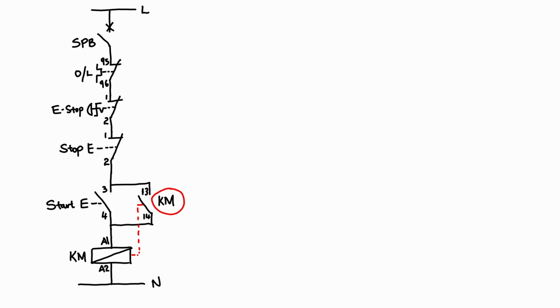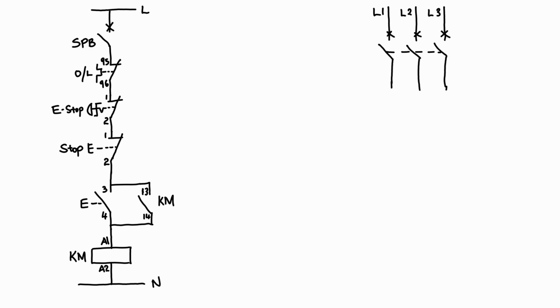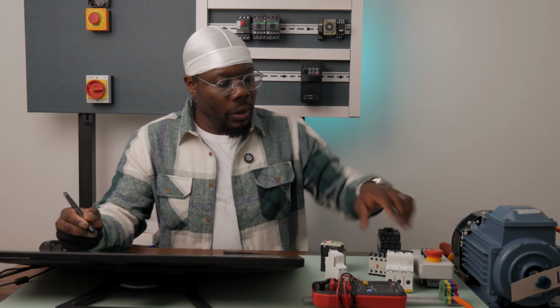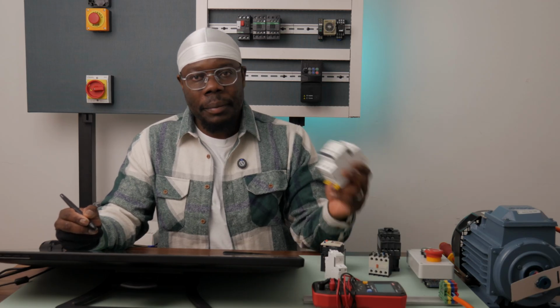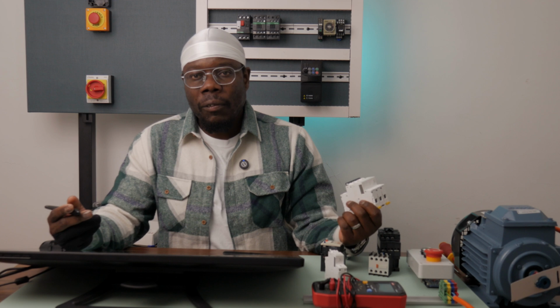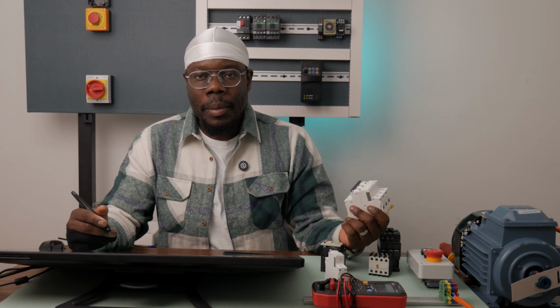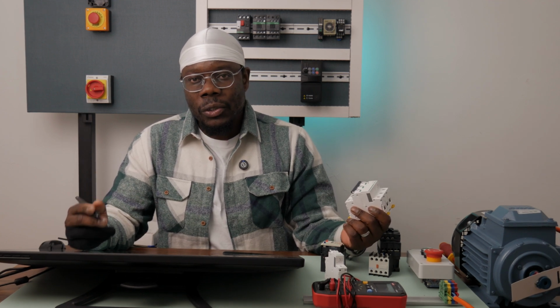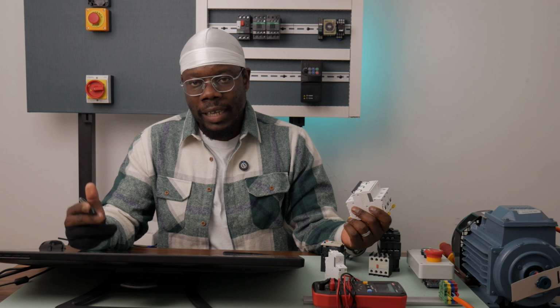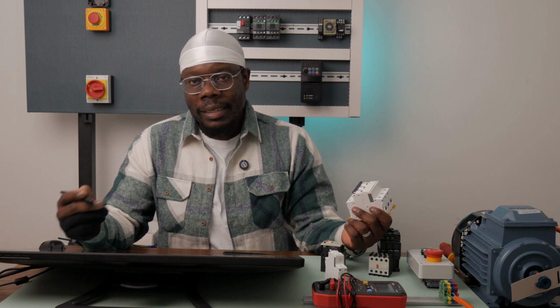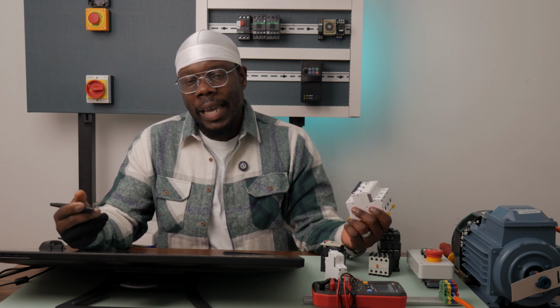Now let's draw the power circuit. You're gonna have obviously your three-phase supply here, L1, L2, and L3, and then I'm just gonna draw the general symbol for a circuit breaker. I'm not going to do anything fancy here. What I have here is a C-type circuit breaker. It's okay for a small motor like this one, but generally you should use a D-type circuit breaker, as we've mentioned before, because a D-type circuit breaker allows for the high inrush currents.